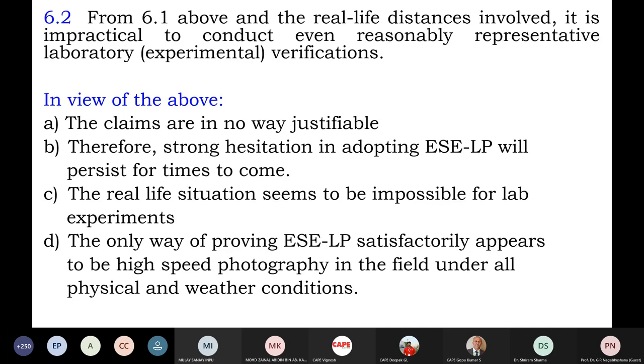Long gaps, humidity, temperature, settling of the dust, etc. With large gaps, it's quite impossible for laboratory experiments. Because if we want to think of testing a 10 meter gap, we will need at least about 4 to 5 megavolts output pulse, that too in outdoor conditions.